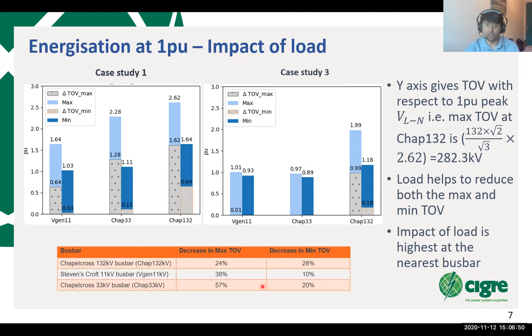Now, the key takeaway from this one is, if we compare these two case studies, once again we see what we observed in the last slide: having a load has a positive impact on the overvoltages observed at the different bus bars. We can see here from the peak values and also the minimum TOV values observed at different bus bars that both the minimum and the maximum TOV reduce at all the bus bars. However, if we calculate the proportion of reduction of the maximum TOV, the bus bar closest to the demand connected has the maximum decrease in TOV.